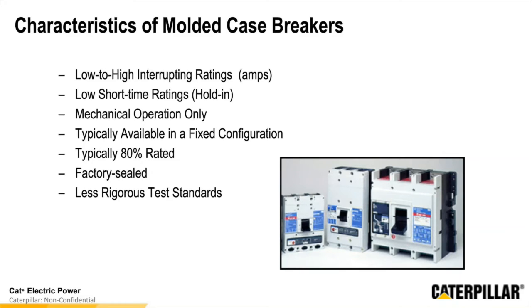Typically, these are going to be the breakers you find closest to the loads overall. They are typically a low short time rating. They're mechanically operated only. They also are available typically only in a fixed configuration, and they're going to be typically an 80% rated breaker. Almost always they're a factory sealed application, which means that the breakers are not serviceable themselves in the field. So if you have a failure of the breaker, you're going to have to take it out entirely and replace it entirely. And they have the least rigorous test standards overall for the different breakers that we've discussed here.